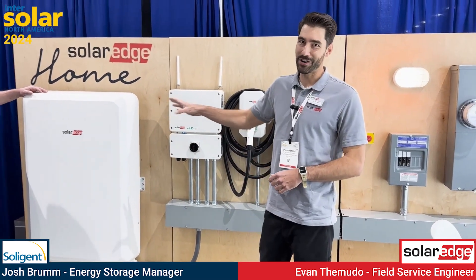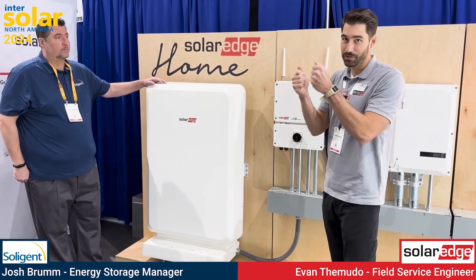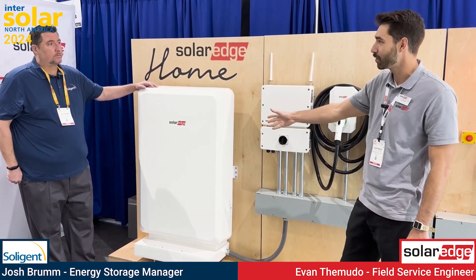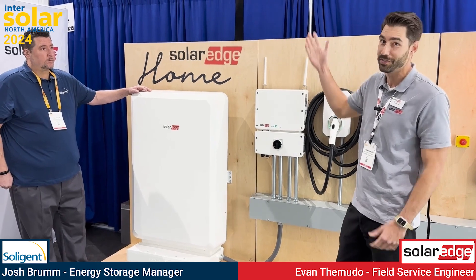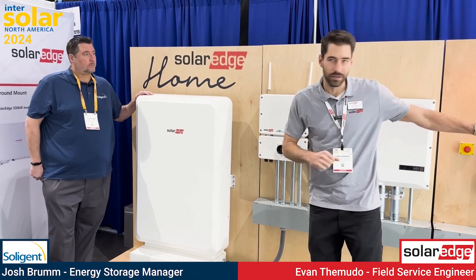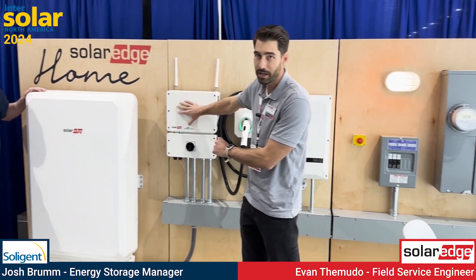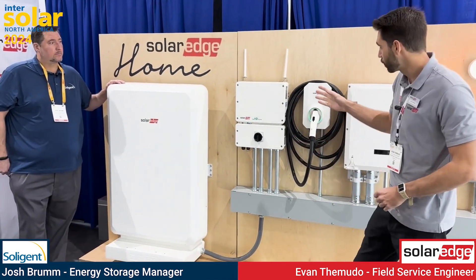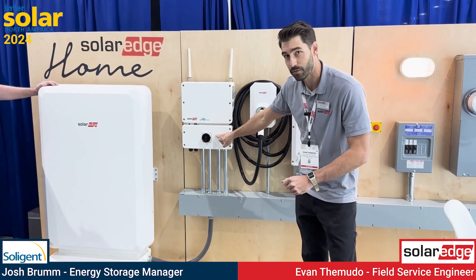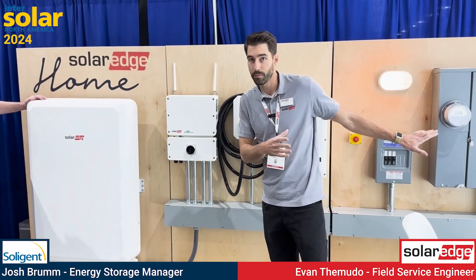These batteries are really simple to install — just like having a solar panel on the roof. We have MC-4s crimped to them and the home runs go straight into the inverter. Same thing with the battery, except you mount it in the garage instead of on the roof. It does not land in the main service panel — it's all sharing a breaker with the inverter. The EV charger lands directly into a 240 outlet inside of the inverter, so no need for an additional breaker.